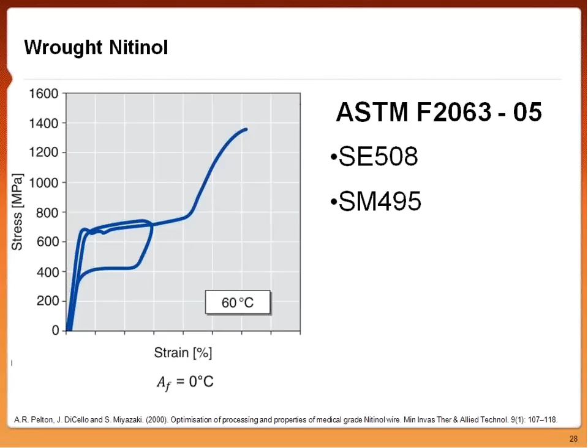What that basically illustrates is this. We see a phenomenon where you can change your AF temperature and you change your stress plateau. And that's actually happening based on our material properties. When we have a higher percentage of nickel inside our nitinol matrix, we can lower our AF temperature. And in terms of a device, we can have a higher stress plateau, meaning you're going to have a stiffer stent. In turn, when we take nickel out of the nitinol matrix, we can increase our AF, and we can have a lower stiffness for our stent.